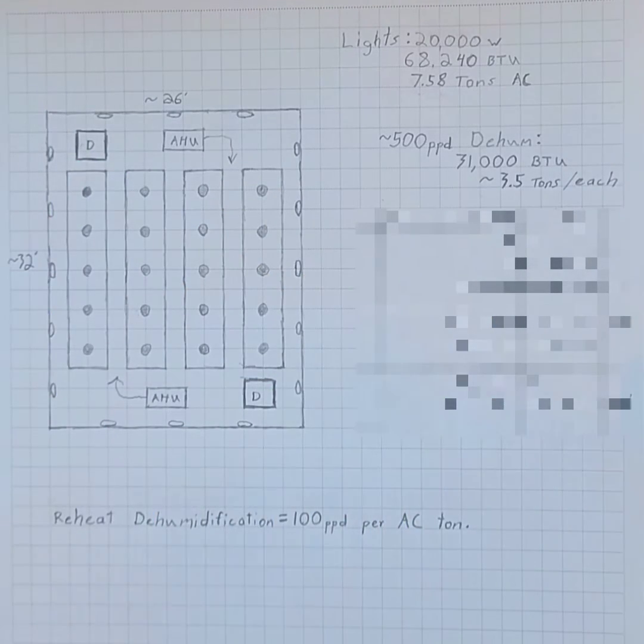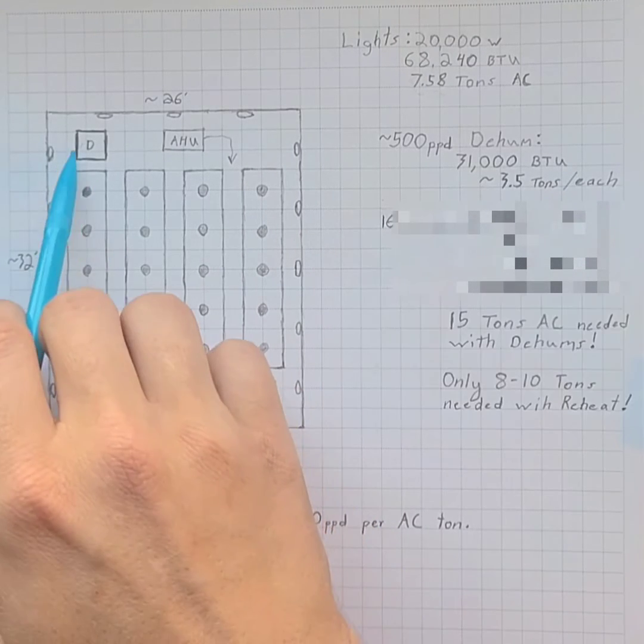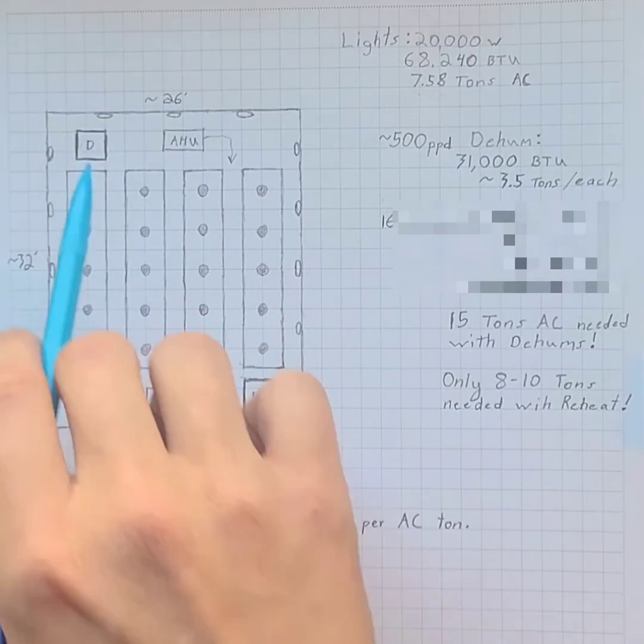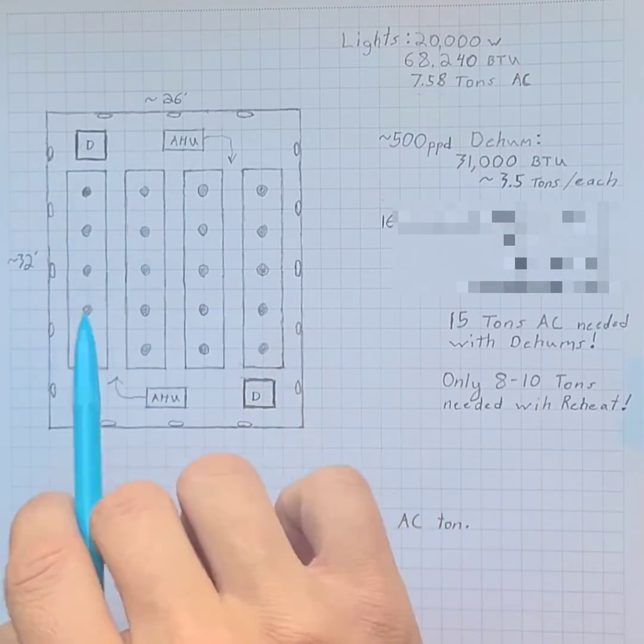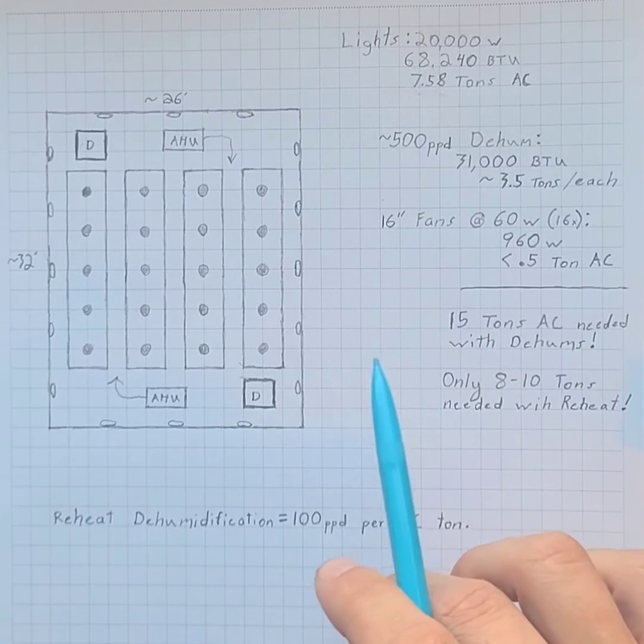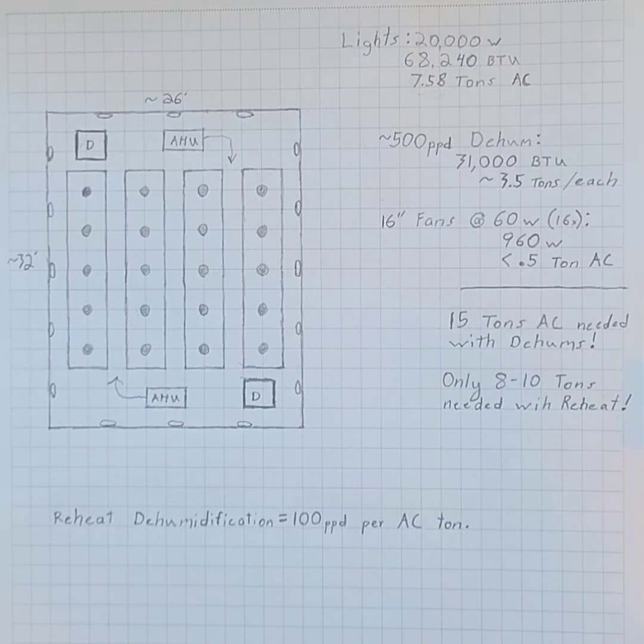The thing is, these dehumidifiers produce 31,000 BTUs each. So each one of these dehus literally needs three and a half tons of cooling just to keep it cooled. So we've got seven tons of cooling just in those two dehus in addition to the eight tons of cooling needed for the lights. So right there alone, you have 15 tons of AC needed just to keep the room under control with those two dehus.